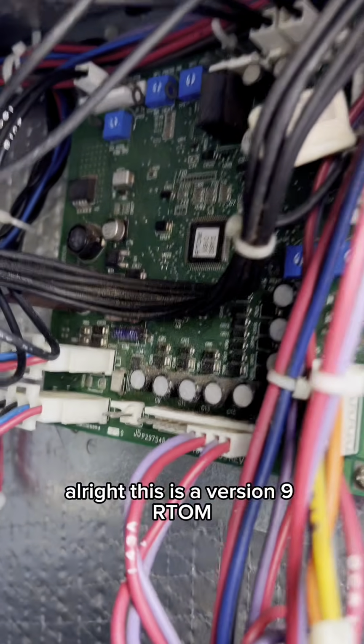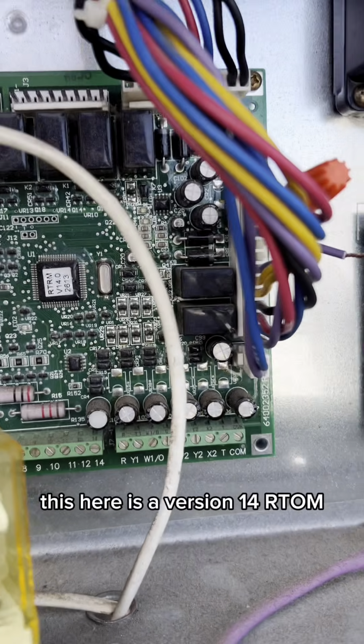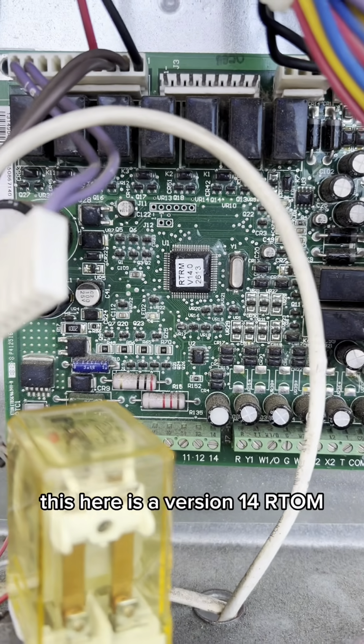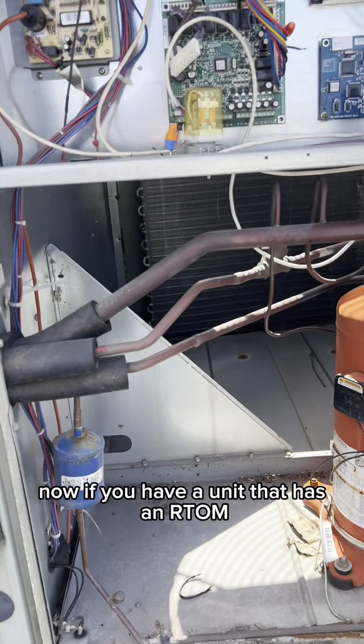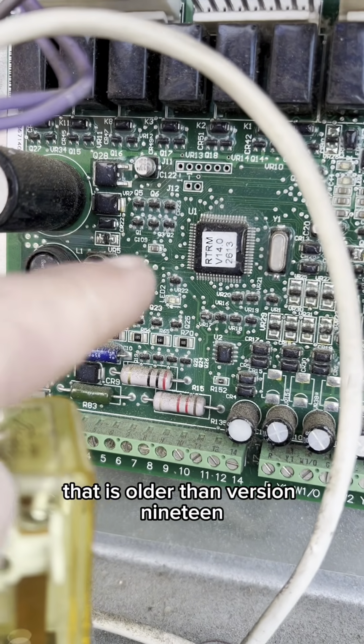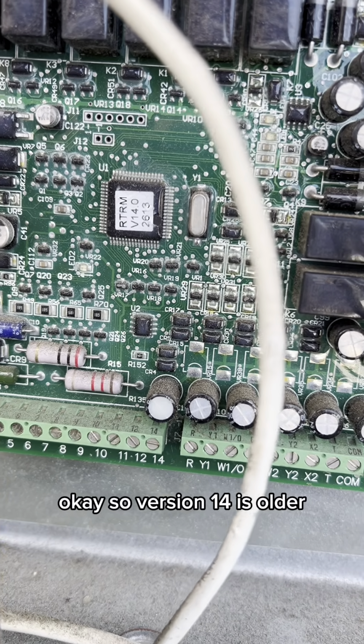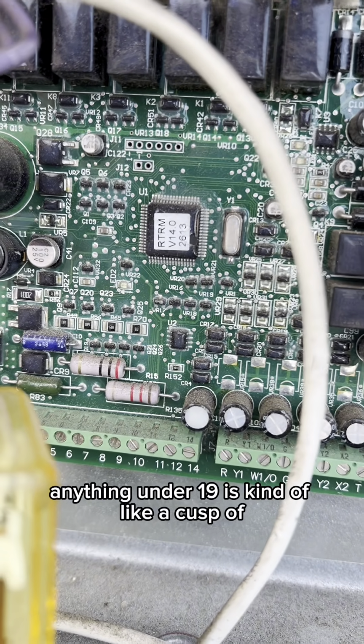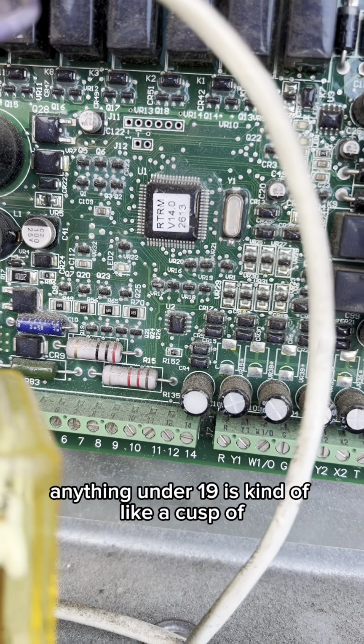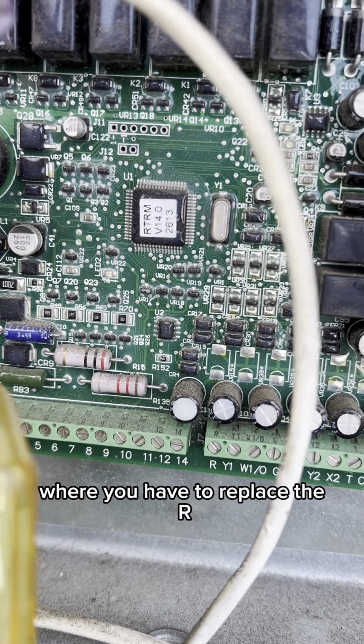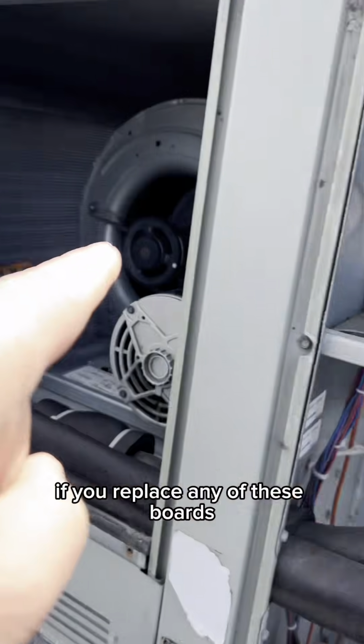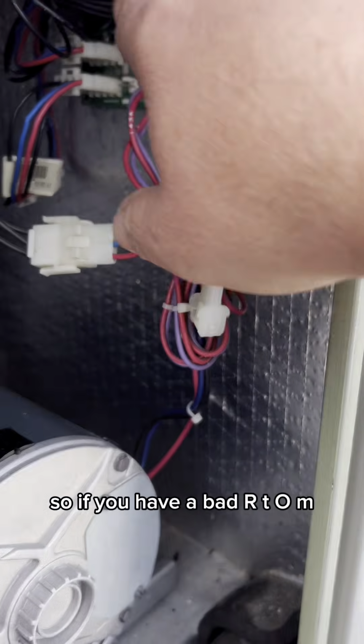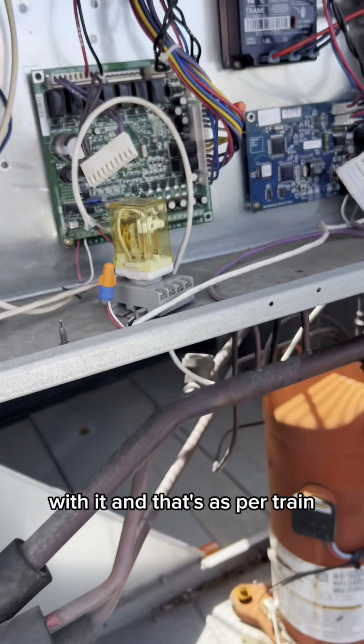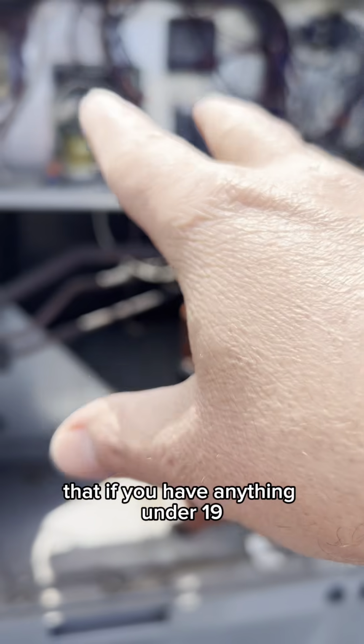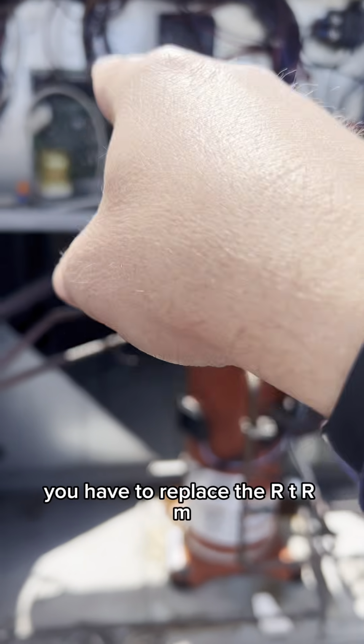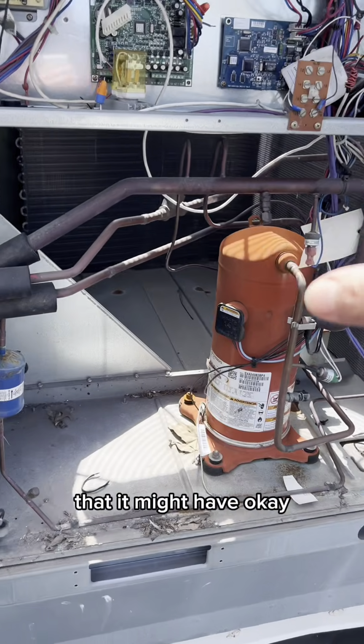But now here's another problem. All right, this is a version 9 RTOM. This here is a version 14 RTRM. Now, if you have a unit that has an RTRM that is older than version 19, okay, so version 14 is older. Anything under 19 is kind of like a cusp of where you have to replace the RTRM if you replace any of these boards. So if you have a bad RTOM, you need to replace the RTRM with it, and that's as per Trane. That if you have anything under 19, you have to replace the RTRM when you replace any of the other boards that it might have.